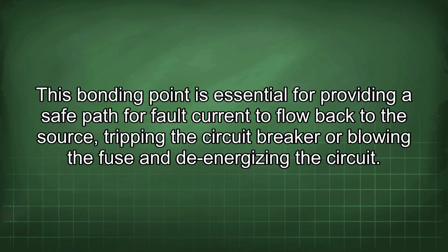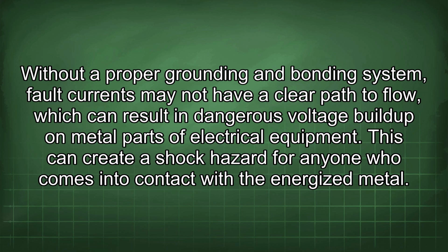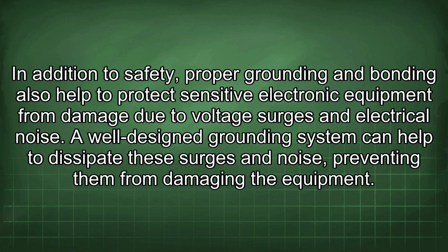This bonding point is essential for providing a safe path for fault current to flow back to the source, tripping the circuit breaker or blowing the fuse and de-energizing the circuit. Without a proper grounding and bonding system, fault currents may not have a clear path to flow, which can result in dangerous voltage build-up on metal parts of electrical equipment. This can create a shock hazard for anyone who comes into contact with the energized metal. In addition to safety, proper grounding and bonding also help to protect sensitive electronic equipment from damage due to voltage surges and electrical noise. A well-designed grounding system can help to dissipate these surges and noise, preventing them from damaging the equipment.